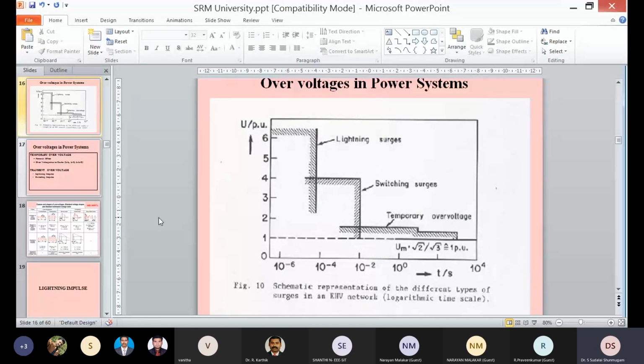When I say per unit, what exactly does per unit mean? Whatever the system voltage, you multiply the system voltage by root 2 and divide by root 3, which will give the 1 per unit value of the given system voltage. I will show the calculation to you.